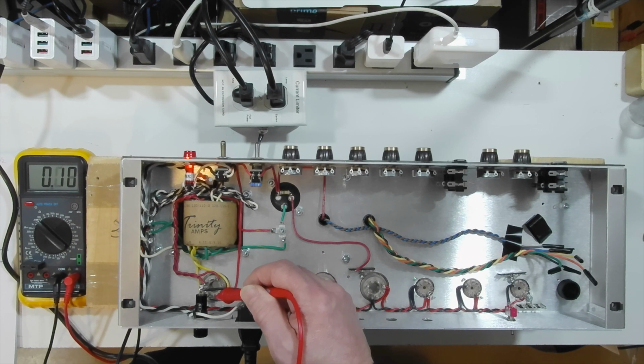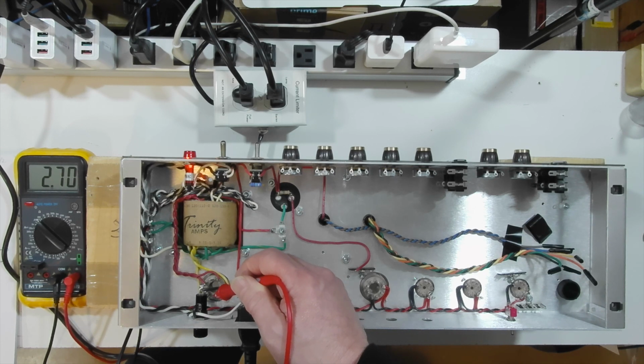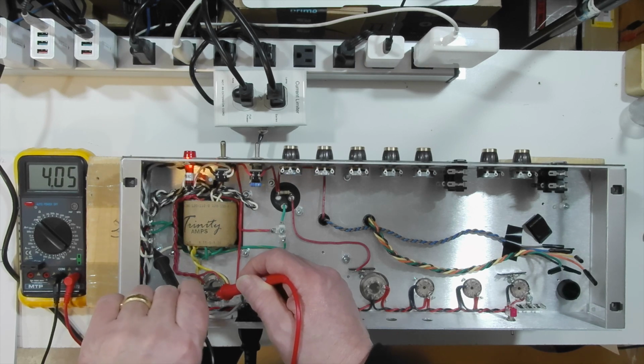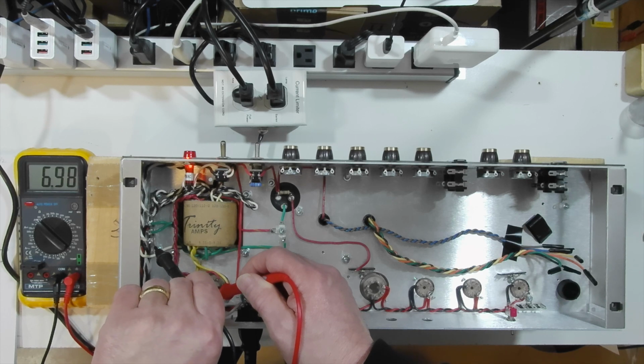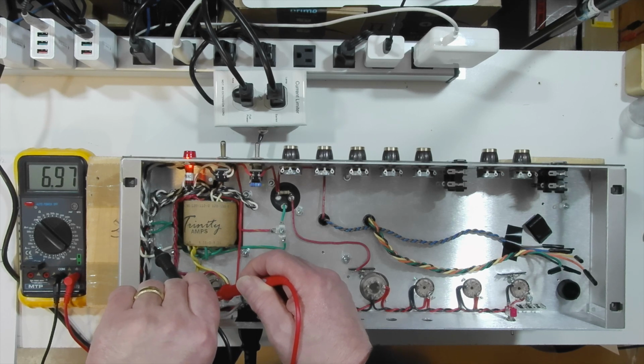We'll put one probe on pin 2 of the rectifier, where that yellow wire is connected—that's the common wire for these windings. The other probe will go here where we've tacked that white wire. There we are, we've got 7 volts AC. Again, 10% high, but normal.